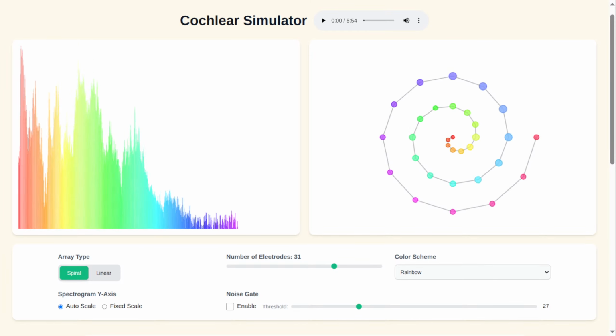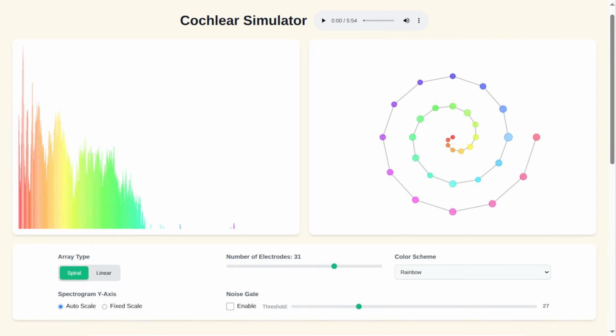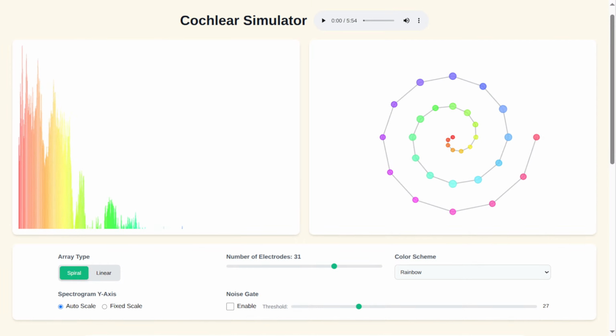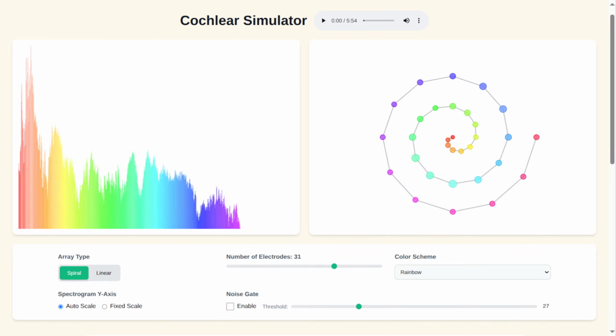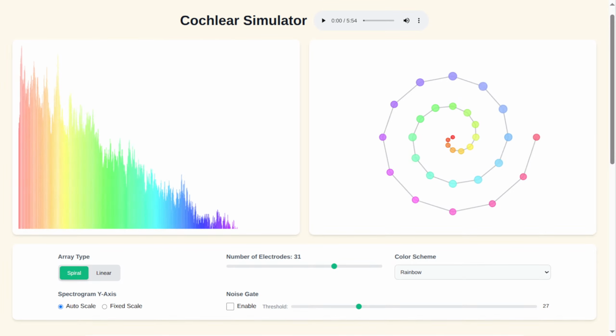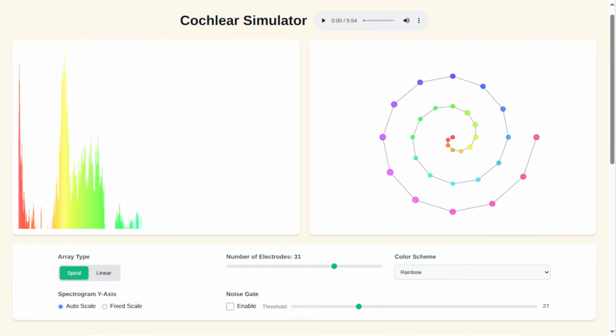I also read about another one, adaptive dynamic range optimization, or ADRO. Yes, ADRO, that's another amplification strategy, different from WDRC. And it has been shown to improve speech recognition, both in quiet and in noisy environments. Any specific conditions where it works best? Particularly when the speech or the noise is coming from either the front or from the side where the CI is located. Interesting. Okay. But even with all this tech, progress isn't guaranteed, right?